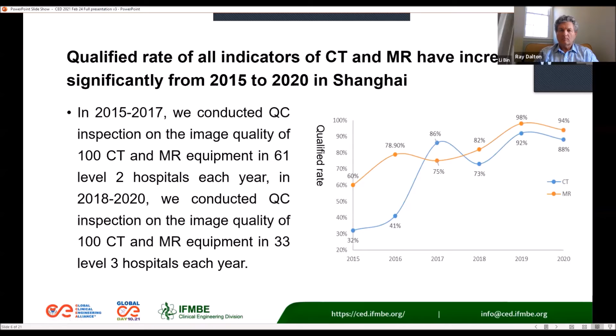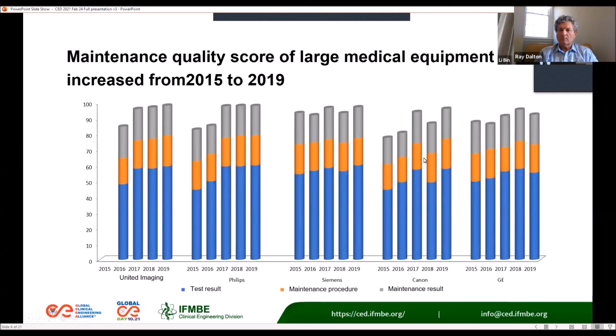Also, for maintenance, we sent an engineer to check the maintenance data and maintenance records, and make an evaluation. We can find that the maintenance quality score of large equipment increased from 2015 to 2019. We can see the different manufacturers, United Imaging, Philips, Siemens, Canon, and GE. This score has increased.